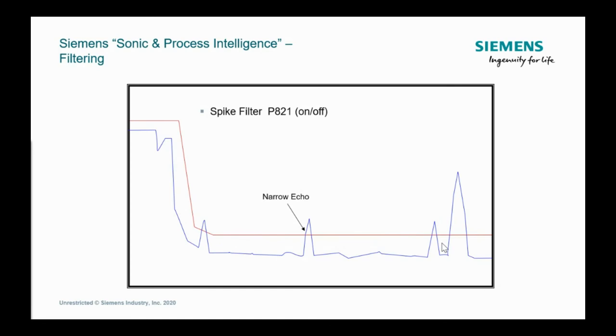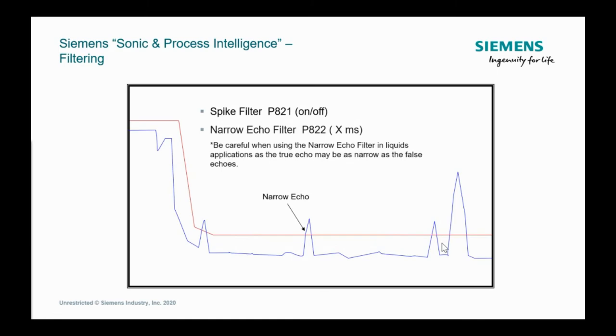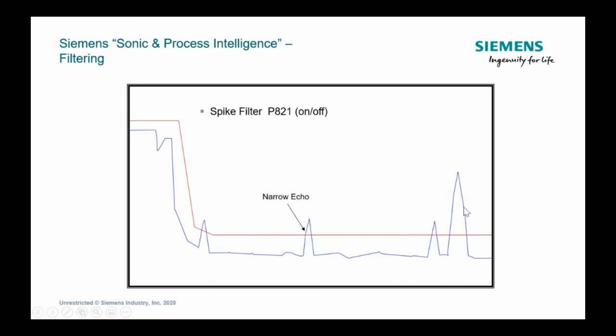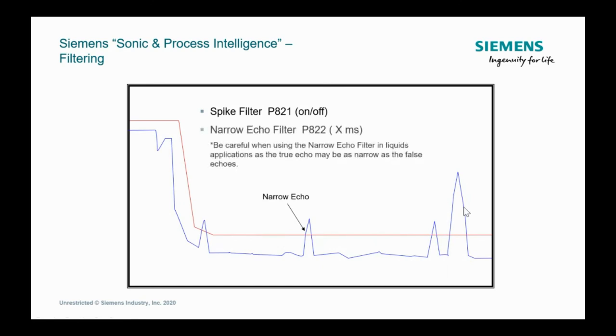There's another thing that you have some control over. The factory default on this is zero, but it is the narrow echo filter. And the narrow echo filter basically allows you to adjust a signal length in milliseconds to allow you to basically chop out some of the narrow echoes. If you notice in this application, how many valid echoes do I have here before I applied the filter? I actually had four. One, two, three, four here. When I applied the narrow echo filter, what you can see is that it'll actually truncate or chop off the top of some of those narrow echoes, and now you're left with only one valid echo in the system because these others have fallen below the TVT.